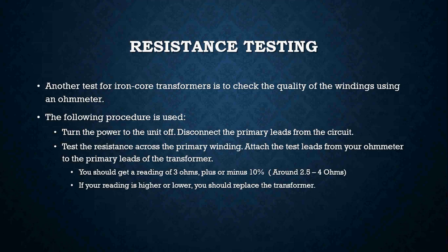Another test you can do on an iron core transformer is just taking an ohm reading, doing a resistance test across it. To do that, the first thing you have to do is unplug the power, shut the power off to the unit, and disconnect the primary leads from that transformer. Now you are going to take a resistance reading across the primary windings. You attach the test leads from your ohm meter to the primary leads of the transformer. You should get a reading of about 3 ohms plus or minus 10%. Depending on the manufacturer of the transformer, you could get anywhere between maybe 2.5 to 4 ohms of resistance, give or take. If your reading is high or low, just replace the transformer.